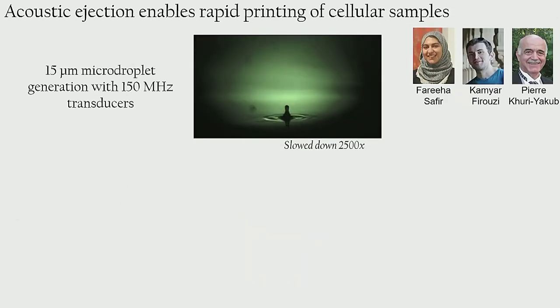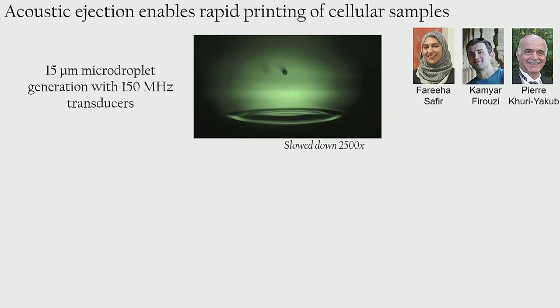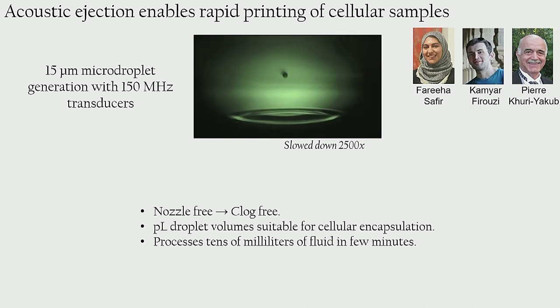Let's take a closer look at the printer. This is a real video of the printing process, where we have focused acoustic waves at the interface between the liquid and the air, generating very controlled microdroplets with a very specific volume based on the frequency of the transducer. This is very advantageous for handling biosamples because you control the volume being ejected with just acoustic waves — you don't need a physical nozzle, so there is no clogging and you are not killing the cells as they are ejected. You also have very precise control on the contents of each droplet, and you can process large volumes of samples in a very short time.